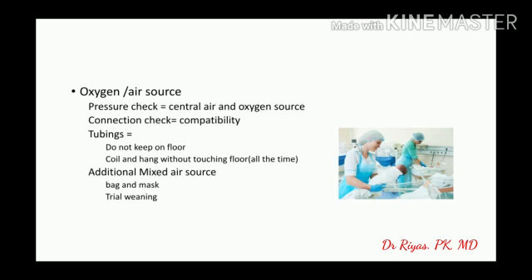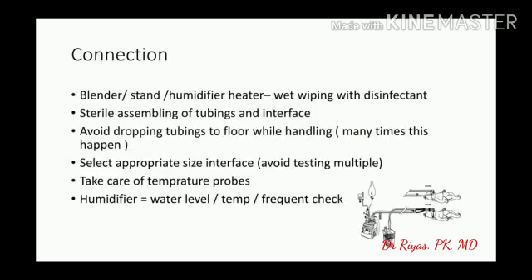We have a lot of wires and tubing hanging behind the crib, that of the warmer, the phototherapy unit, the infusion syringe pumps, oxygen and suction tubing. They all are extra long and often lie on the floor. Make sure that the extra length is coiled and never touching the floor, and keep them clean. Utmost care is to be taken during assembling the set to avoid breach in sterility. Avoid dropping of the tubing while handling them, and many times this happens, as the tube becomes unsterile and needs to be discarded. Select the appropriate size of interface so that you do not need to open more than one at a time. The probes along with the humidifier should be cleaned and kept covered when not in use.